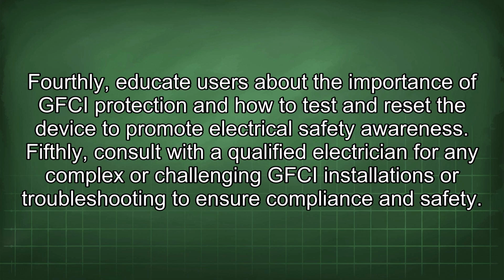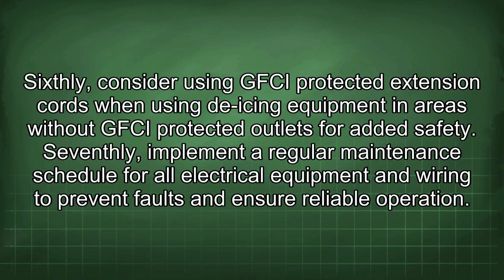Fourthly, educate users about the importance of GFCI protection and how to test and reset the device to promote electrical safety awareness. Fifthly, consult with a qualified electrician for any complex or challenging GFCI installations or troubleshooting to ensure compliance and safety. Sixthly, consider using GFCI protected extension cords when using de-icing equipment in areas without GFCI protected outlets for added safety. Seventhly, implement a regular maintenance schedule for all electrical equipment and wiring to prevent faults and ensure reliable operation.